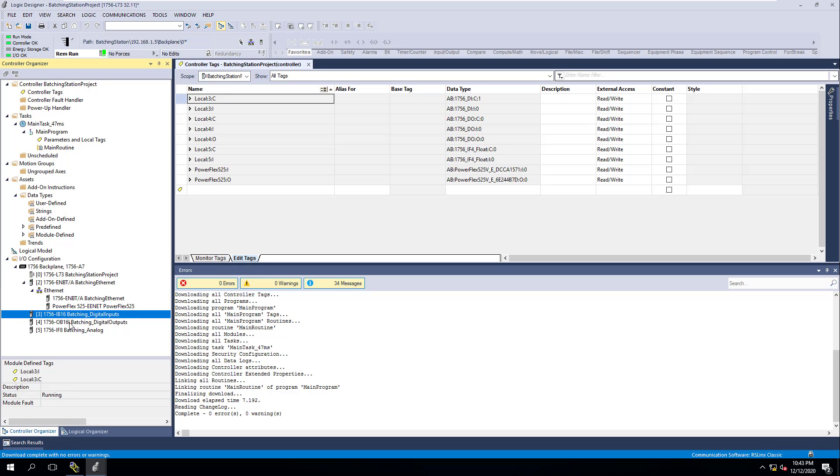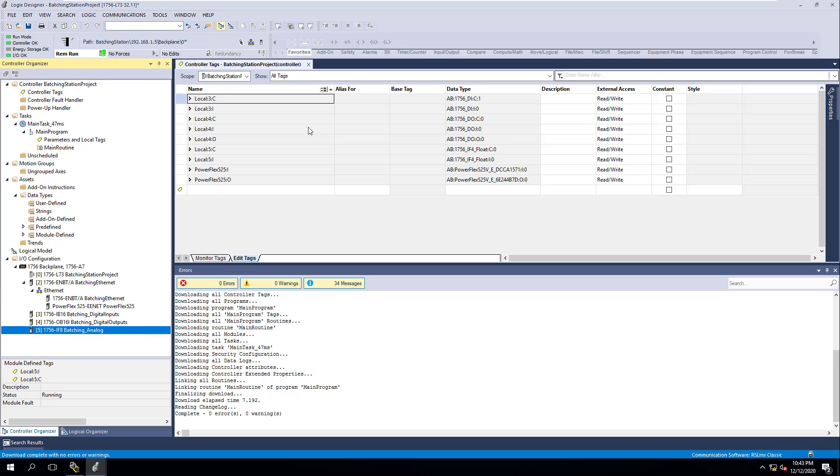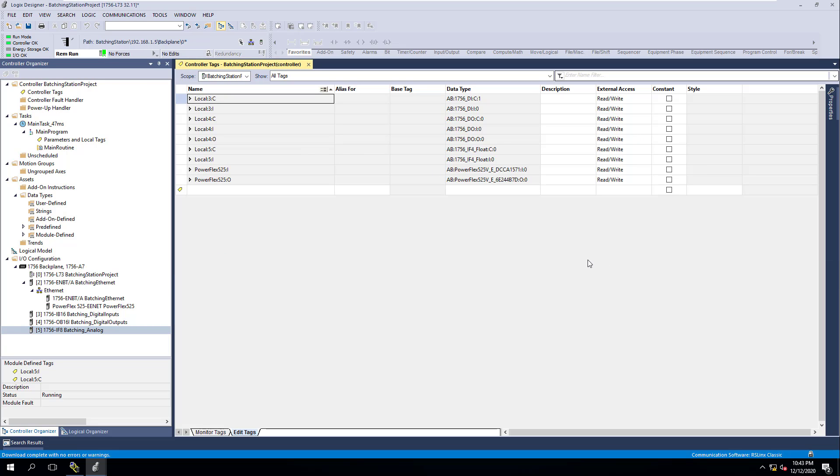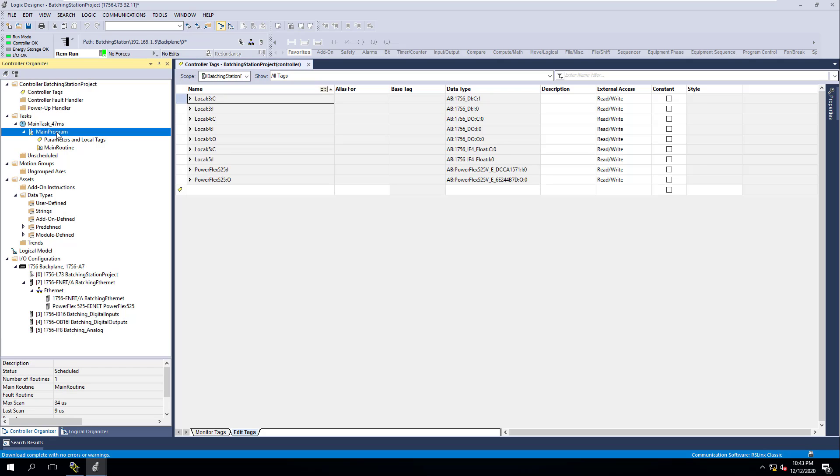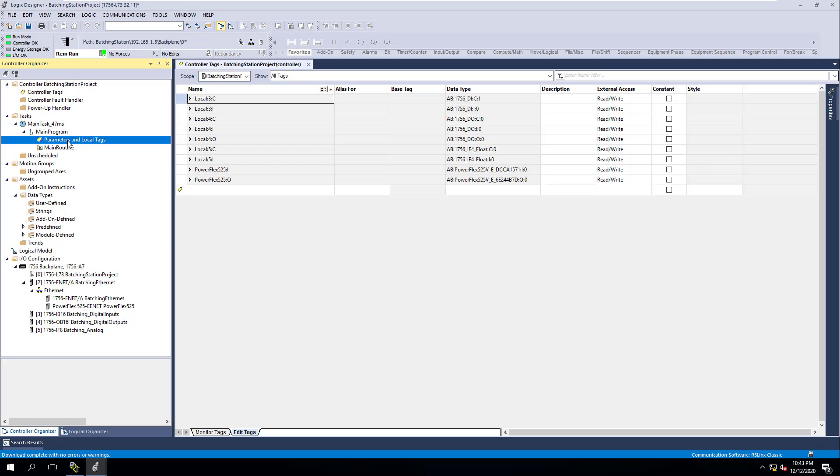What we have done is I've showed you how to properly configure things. Now I want to highlight and let you understand: when it comes down to your real world IO or anything in your IO tree, that is a global tag, meaning that is a controller scope tag. In Control Logix, you have two types of tag structures. You have program scope tags that you can make and use at your program level, which you can see right here, your program tags, the local tags.